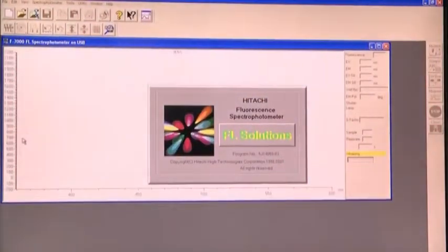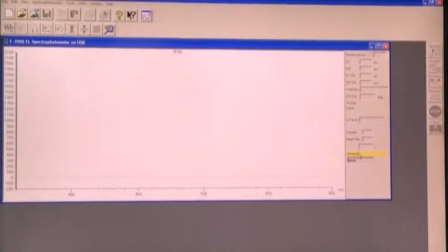And once we click it, we can see here this initialization is taking place. Kindly remember, do not proceed with any experimental reading when initialization is going on, and do not open the lid also. After that, parameter setting is taking place, and we can see these are all inactive out here because initialization is still going on. And once these menus are active, we can be sure that this initialization is completed.